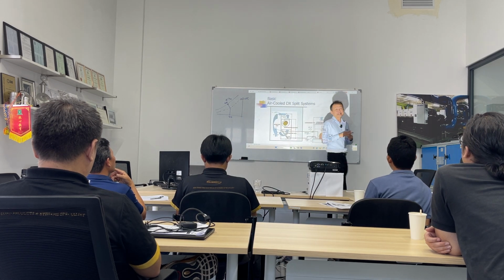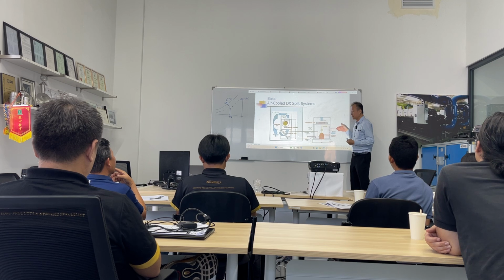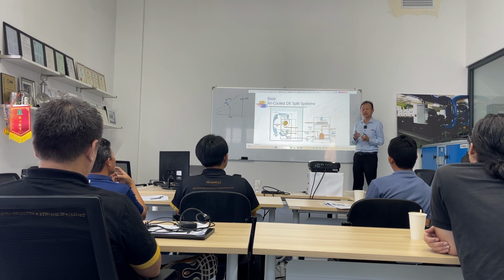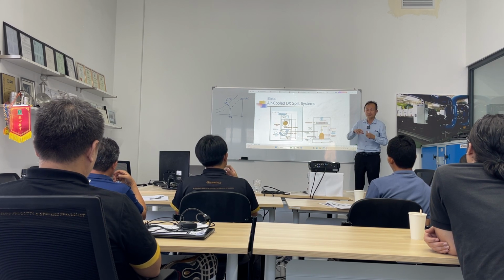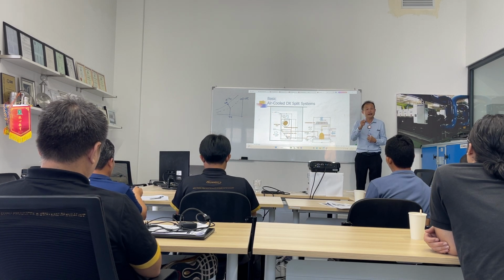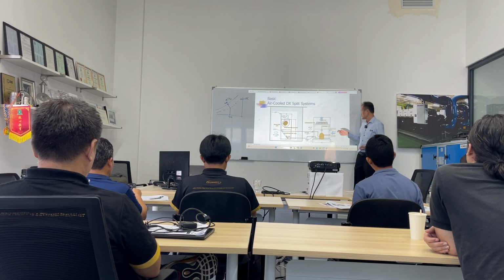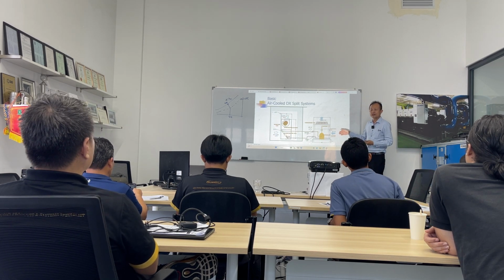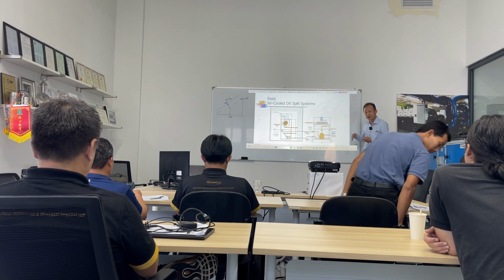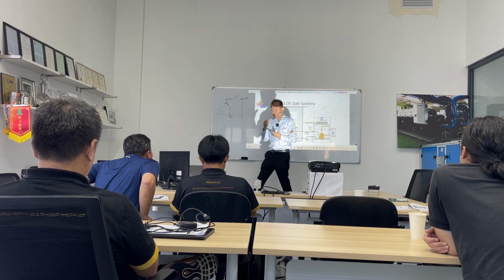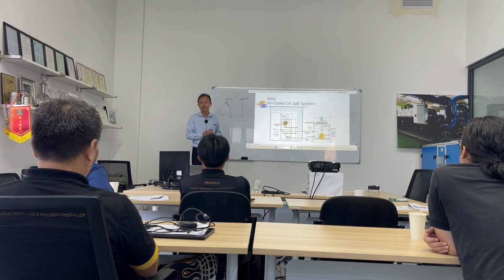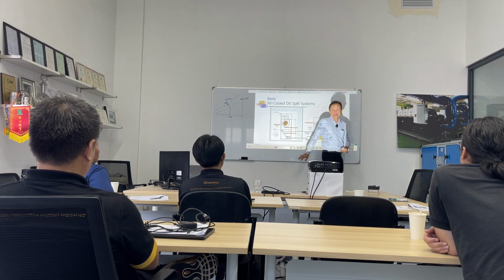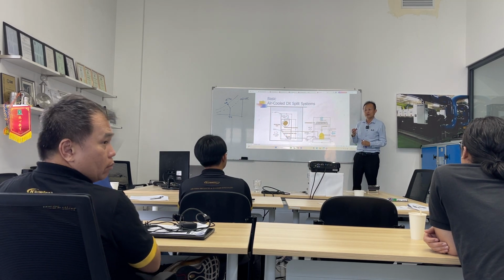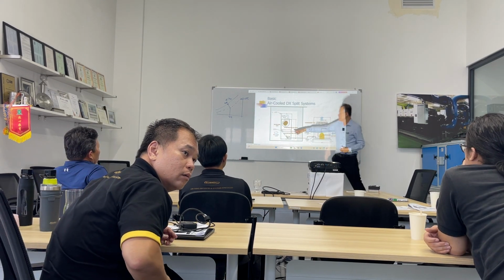There are many terminologies used. You can say this is outdoor air temperature. Some suppliers say, what is the outdoor air temperature for the condenser? But some consultants specify in a different way. They say, I want the air entering condenser coil temperature to be 95. Because this temperature actually affects the capacity and also the power consumption. Of course, the condenser air affects the power consumption more. Capacity is not very substantial, but the air entering evaporator temperature affects it a lot.